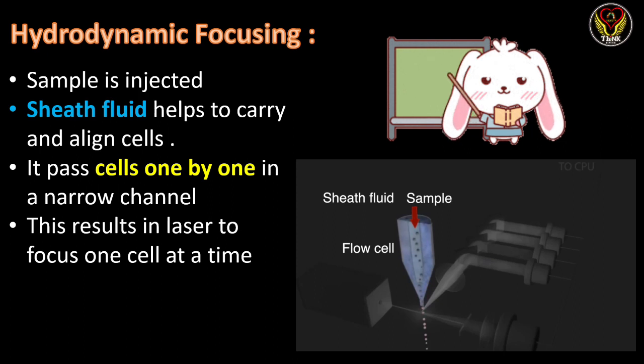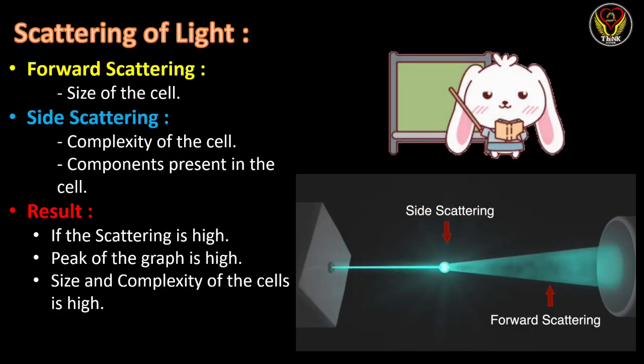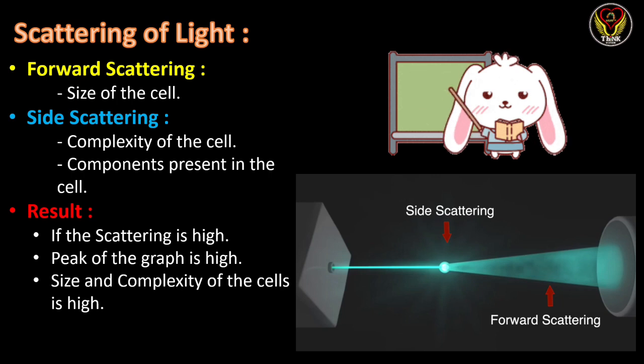The second principle is the scattering of light — the key piece of flow cytometry. This principle means that if we place a shining stone on the path of light, the light gets deviated, reflected, and scattered in all directions. This scattering is based on the structure and size of the stone. The same happens here: instead of a stone, there is a flow of cells, and the light source is a laser. As the laser focuses on the cells, it gets scattered. There are two major types: forward scattering and side scattering. In forward scattering, the light scatters in a forward direction, whereas in side scattering, the light scatters in all other directions.